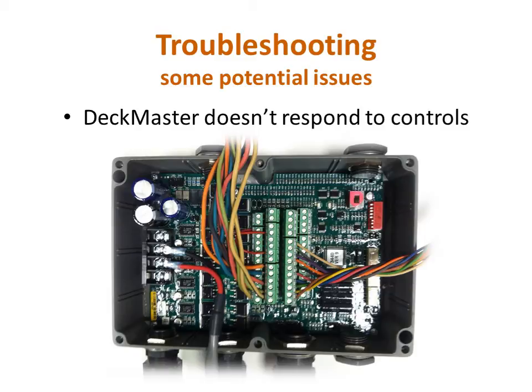In this first example, the monitor does not respond to the controls. Now, this is a rather broad statement, so let's begin to narrow down the potential causes. If none of the controls are responding, the first thing to check is that power is being supplied to terminal block 2, or TB2, pin 2, and is grounded to pin 3. If there is power to the logic box, then move on to terminal block 1 and check pins 10 and 24, which are the common pins that supply power to any controller wired to them.